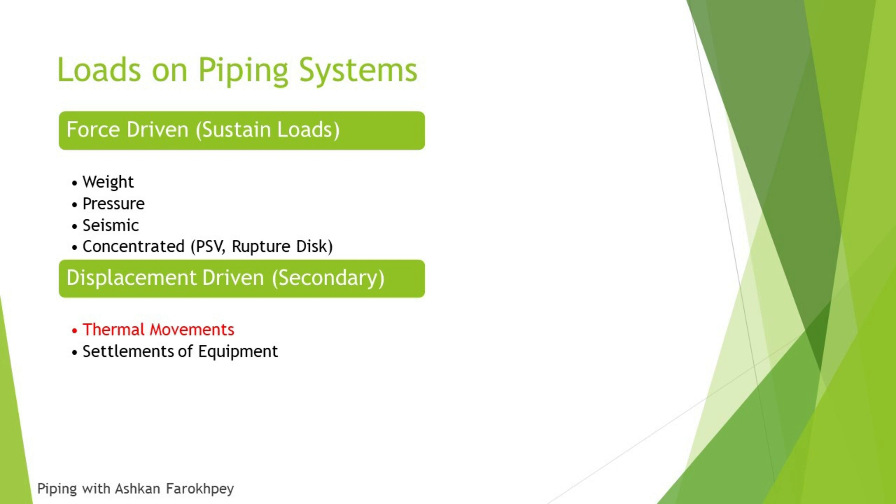The second one is settlement of equipment. For example, consider a tank which is full of water. A huge tank may be settled during the first weeks or months of its operation. It may have some settlements around 10, 15, or 20 centimeters, and in these settlements some forces and loads are added to our piping system.